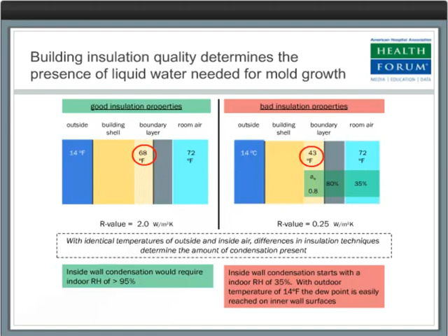If you have great insulation in your building, you need a very high relative humidity, over 95%, before you start getting condensation on a surface and mold growth. If insulation quality is poor, you could start getting condensation at a relative humidity of only 35% in this example. But really, with the same temperatures, it's the difference in insulation technique that determines whether you'll have liquid water and then mold present.